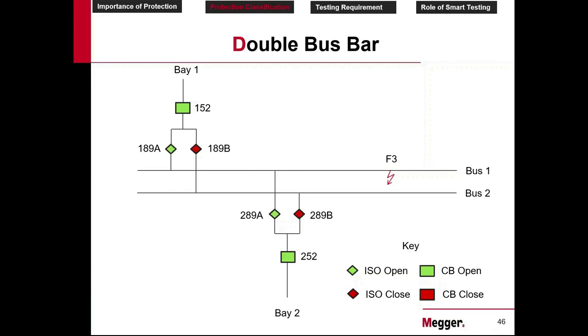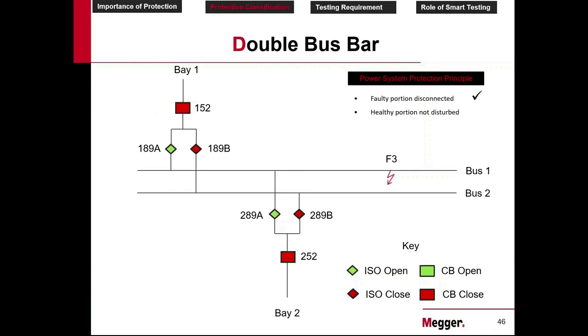Then after some time delay, we switched and we brought back this bay 1 and bay 2. So that means there is going to be an interruption. That interruption is going to be for a long time because isolators typically take around 15 to 20 seconds to operate.